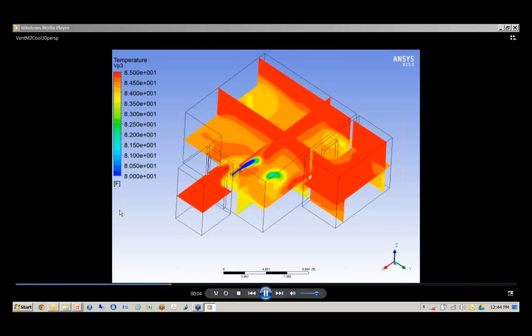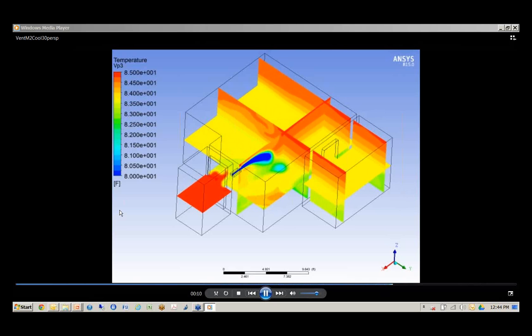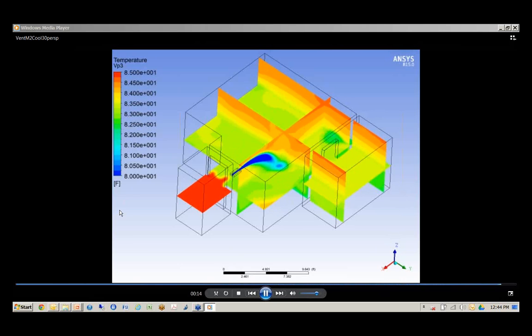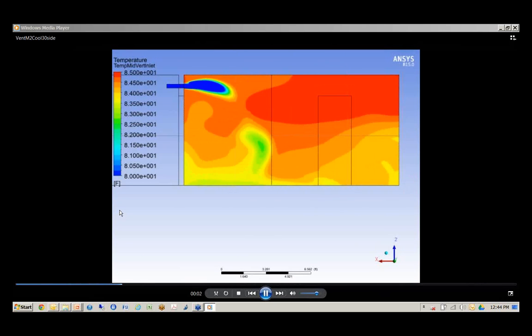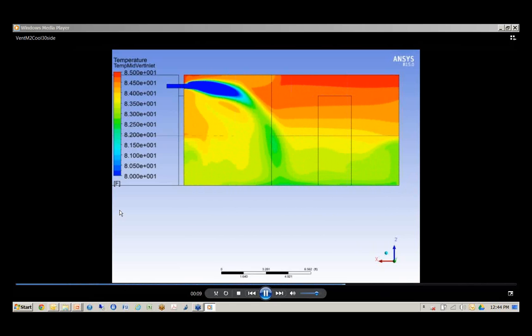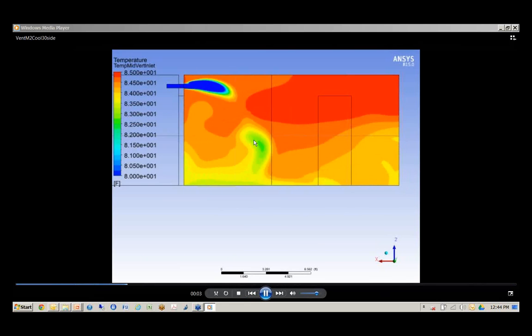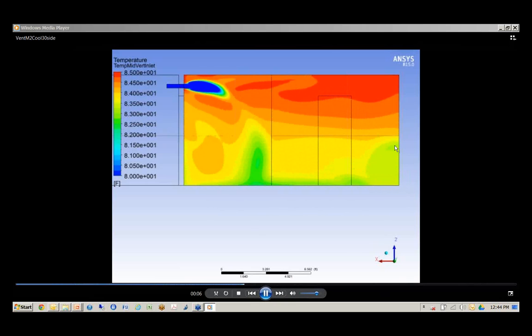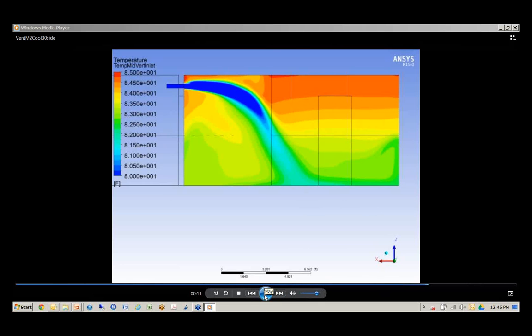This is a shot of the same room, again, with this standard lower velocity airflow coming out. And it appears to almost be like a water hose trickling cold air into the building, pouring it and filling it up from the floor to the ceiling. Much less mixing, much less engagement in the room air temperatures. And if you think about your thermostat being at mid-level, well, you might meet your thermostat at a certain temperature if that middle line there is where the thermostat is, and the green bubble is what your temperature is supposed to be. Well, this might turn the system off right here, and you've still got a high level of stratification in the building.